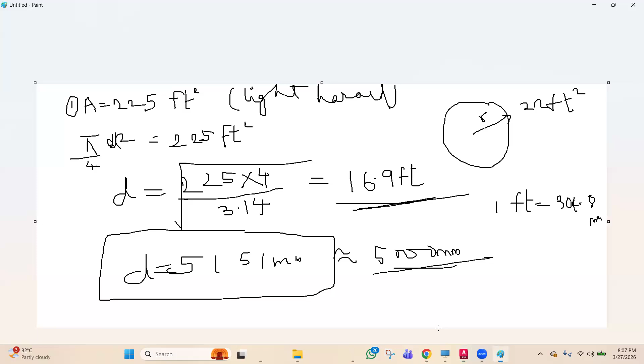Sir, you have taken that radius as 2500, right? Radius means this radius you're saying for the circle? Yeah. No, for the circle the diameter is 5000 mm. So radius is d by 2, 2500 mm. Okay. Sprinkler to sprinkler, we should take 5 meter, roughly, no? Yeah, 4.5 meter is acceptable. Sir, we should take the maximum, means.